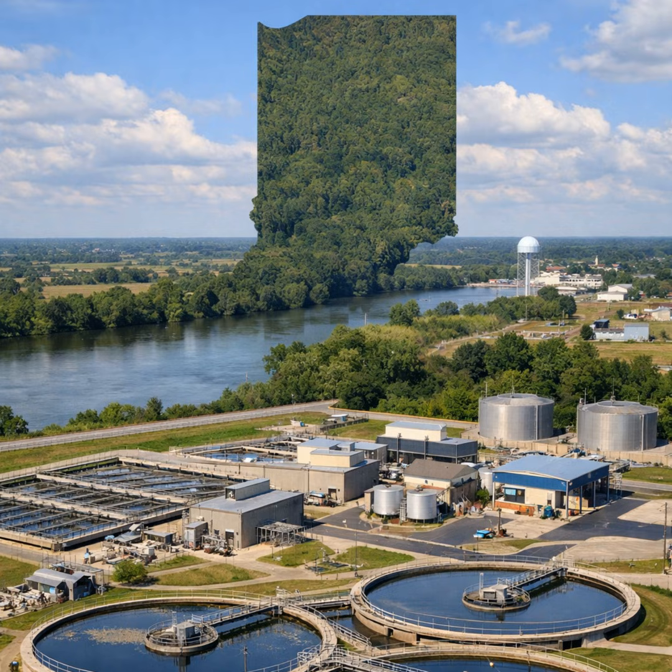Stuck digester. A stuck digester does not decompose organic matter properly. The digester is characterized by low gas production, high volatile acid and alkalinity relationship, poor liquid-solid separation. A digester in a stuck condition is sometimes called a sour or upset digester.